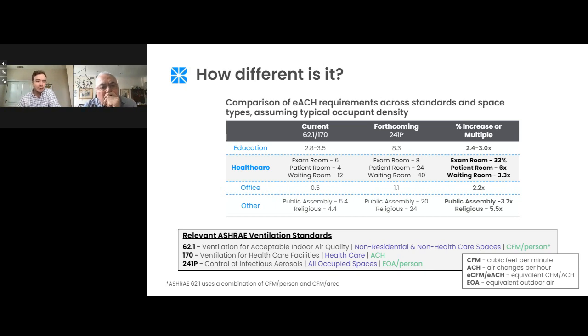And there, if you look about in the middle with the gray background, you can see what Dr. Nardell was talking about. 6 to 12 air changes in patient rooms, I believe it was 4 in ASHRAE 170, but in that range typically in most healthcare spaces. In the forthcoming standard 241P, you see that going up to the range of 8 to even all the way up to 40 EACH in waiting rooms. And what that looks like is a significant increase across the board.